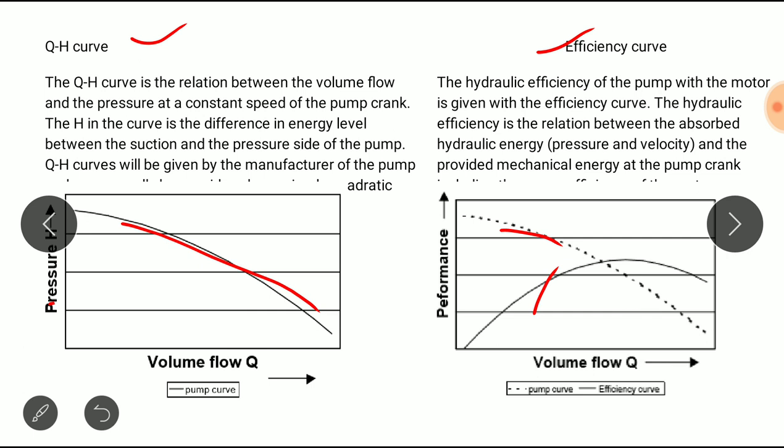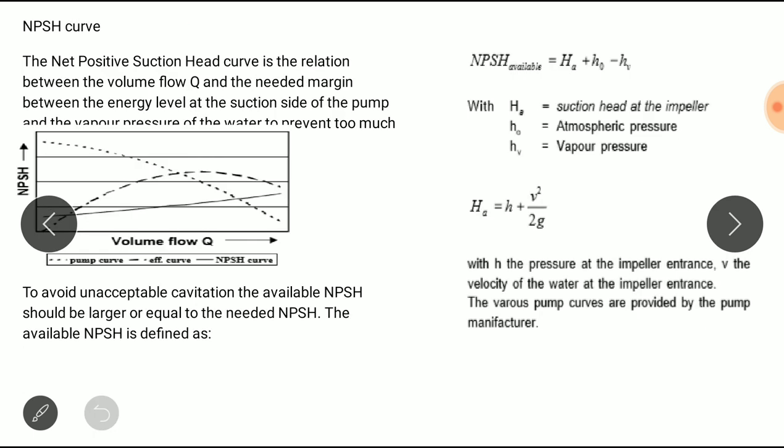The third one is the NPSH curve. NPSH means Net Positive Suction Head. The Net Positive Suction Head curve is the relation between the volume flow rate and the needed margin between the energy level at the suction side of the pump and the vapor pressure of the water. It should not be too much. We should have to take care that the negative pressure should not be less than the vapor pressure so that there should not create any cavitation.